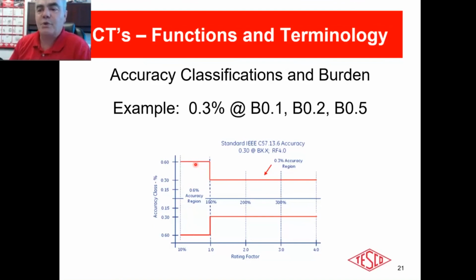What's the other issue with the older transformers? This number right here, 10%. Do you know what happens to the accuracy once you drop to less than 10%? So on a 400 to 5, that would mean once you drop under 40 amps, you don't have any accuracy. You're basically getting no bill, okay? So what does that mean?